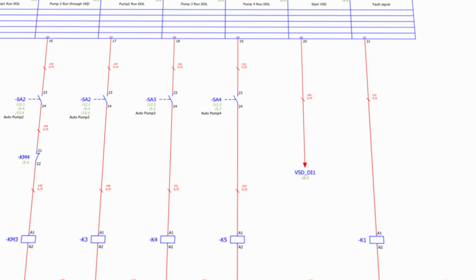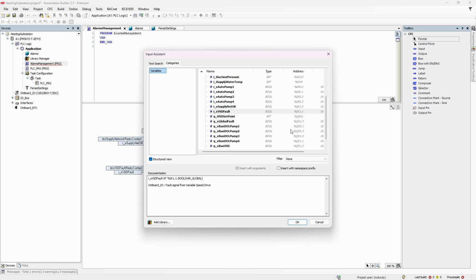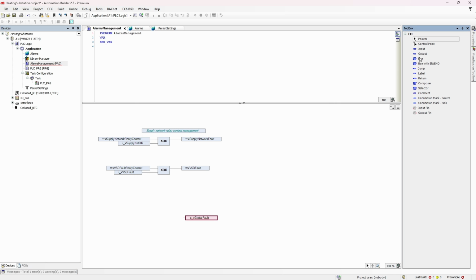We also have this global fault output signal, which is supposed to be activated in case any alarm or fault occurs. So we add an OR operator, connect the output to the DO mapped variable, and then connect the fault variables to the inputs of the OR operator. Are those all the alarms we would have for the whole project? No, not really. We'll also need to handle various sensor-related alarms and pump abnormal behavior.